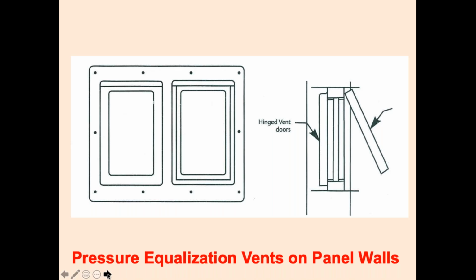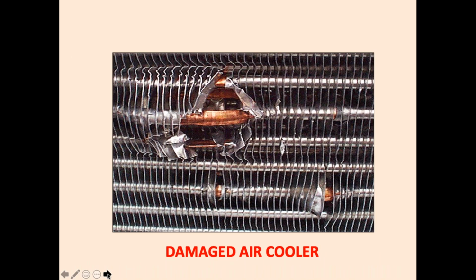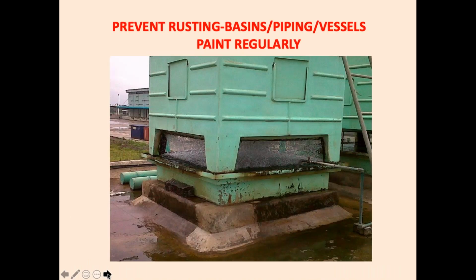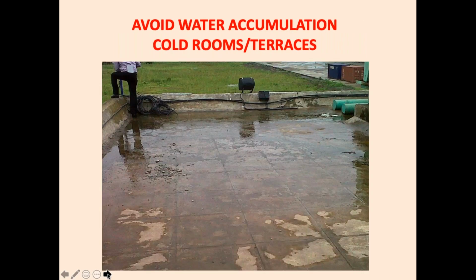The people have not provided the ventilation valves, and an entire cold storage worth crores of rupees has collapsed when the temperature started getting down from ambient temperature, because the air volume goes on reducing as the air is cooled, and the delta P is created, which forces the panels to collapse. Don't use damaged materials. Accumulation of cooling tower piping overflowing. This is regular; I have seen it in many places on the terraces, it's full of water. Avoid these practices. Avoid this water accumulation.